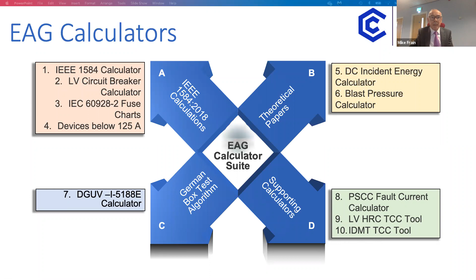What I've done is tier the approach. At the bottom, tier 3 - you would only need to know the fault level to make those calculators work, so just a minimum fault level. You might not know the exact fault level, but you know it's not below a certain figure, so it's aimed at lower level faults. Tier 2 circuits need the actual fault level but not the time current curve. Tier 1 circuits, like the IEEE 1584 calculator, need both a time current curve and the actual fault level - and there are supporting tools to help you get to that point.